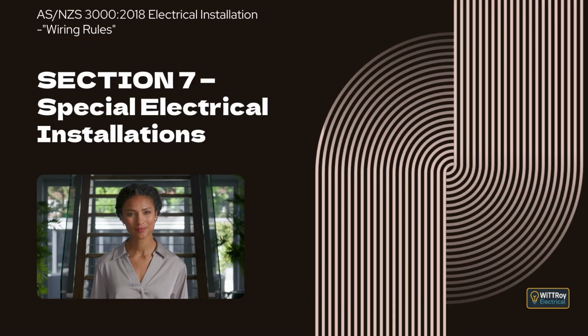It further explains that exposed conductive parts supplied by a separated circuit must not be connected to protective earthing conductors, exposed conductive parts of other circuits, or the exposed conductive parts of the source of supply. It explains that cables and flexible cords must be protected against mechanical damage or arranged so any damage is readily visible. Clause 7.4.4 Switching devices.